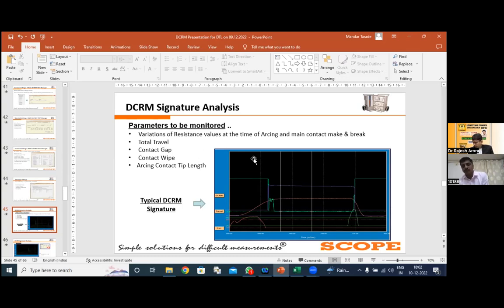Here with the green color, we have indicated the resistance curve, and with the blue color, we have indicated the current curve, which is passing through your DUT and the resistance of your arcing as well as the main contact. Here with the red color, we are indicating the travel traces and the coil current. In case of coil current, it is for the R phase or cumulative, depending on the connection. If you are taking the combined coil current, that is the summation of C1 plus C2 plus C3, the closing coil or the tripping coil, you get the summation of the coil current on your screen.